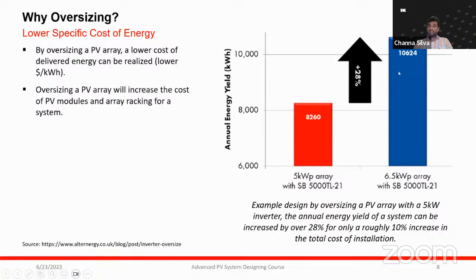These numbers come from a simulation, obviously. Manual calculation is very difficult, but you can do a simulation run using software like PVsyst, Helioscope, or any other independent software and see what the energy output would be. If you're using simulation software, the simulation reports already show the amount of power clipping, or the energy being wasted because of the oversizing factor. So in this case, if you oversize the array by some 30%, this much energy yield appears. But by their calculation, it will increase the cost by 10%. Why does it increase? After the inverter, everything stays fixed. It may only additionally cost for the 1.5 kilowatt of PV array, some mounting structure, and some labor.